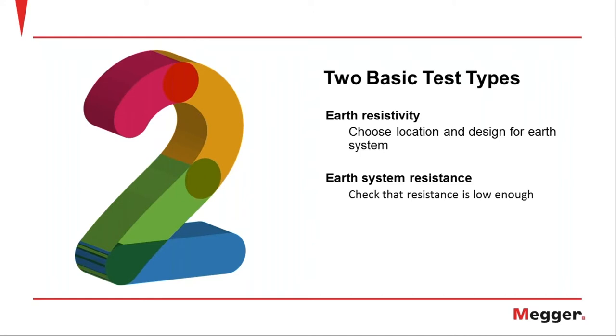The second part is resistance. This is where you have an electrode that's buried in the soil. This is your ground rod or by extension, it can be something much larger like a grid. A big grid underneath a substation is really doing the same thing that a ground rod does, just putting more metal into the ground to decrease the resistance.